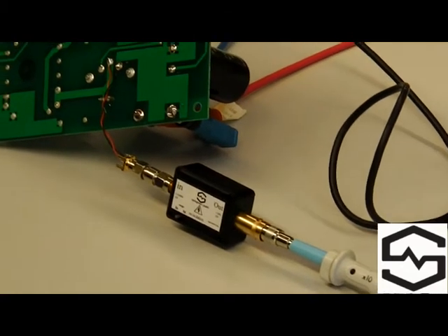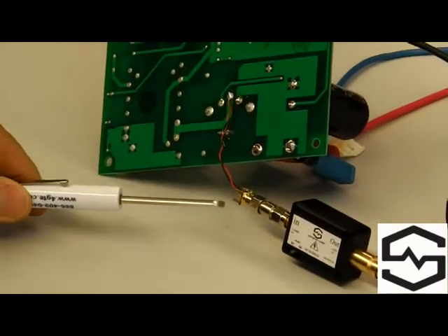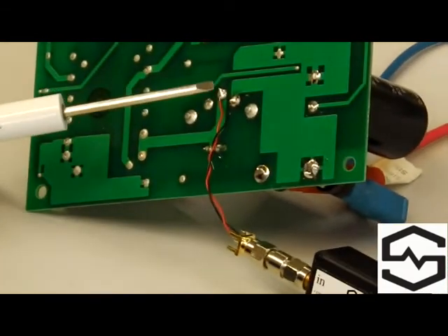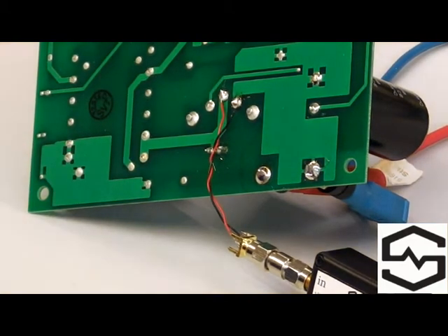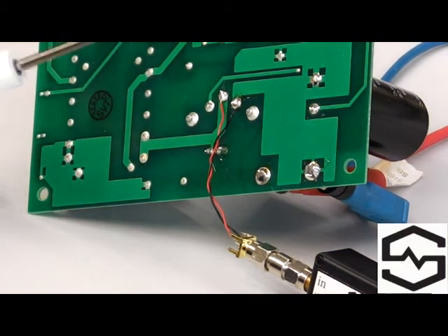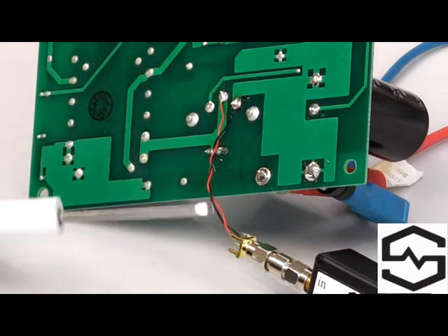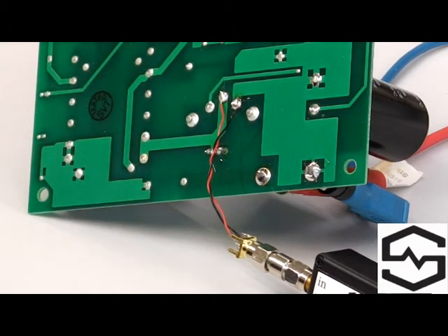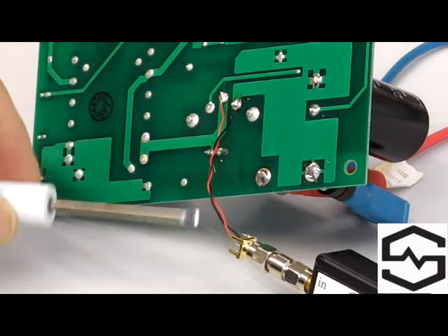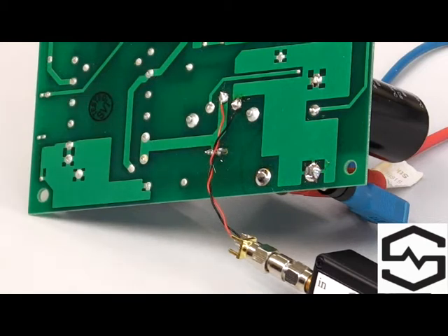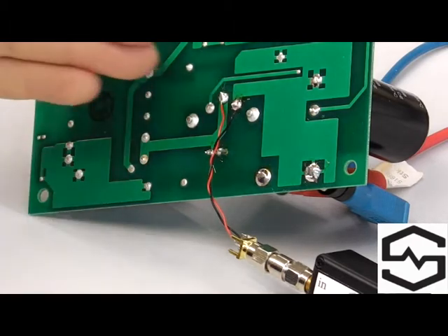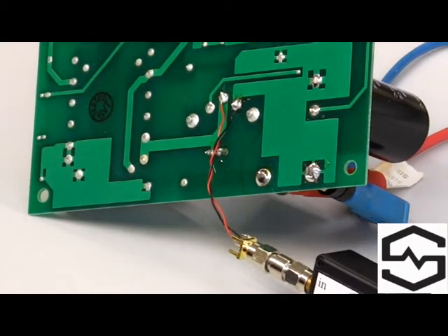Other things about the test setup worth mentioning: the distance between the device under test and the SMA cable should be kept very small. We've got a distance here of about 5 centimeters, which is close to the maximum that's good for high-speed measurements. We're looking at a voltage of about 1 volt across the MOSFET when it's conducting, sometimes less, so any inductance here will cause common mode currents which will upset our measurements.